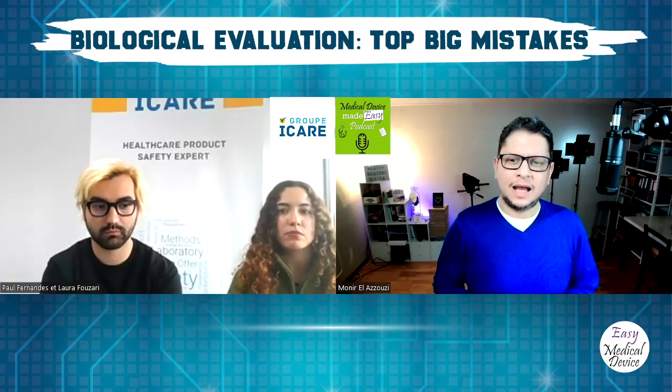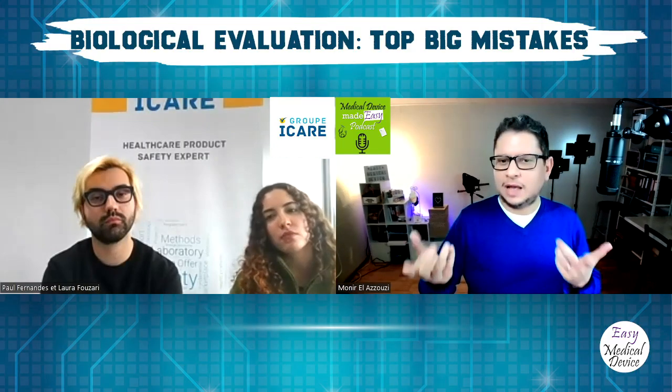Apart from these regulation issues, it will also evolve if you change your raw material in your medical device, or if your supplier changes, because a small modification in your medical device can lead to a big, important change for the patients in the end. So I suppose also, as you said, if your supplier changes, you have to redo maybe some of those tests, or you have to justify why you should not redo some of those tests, etc. So there are a lot of those things.